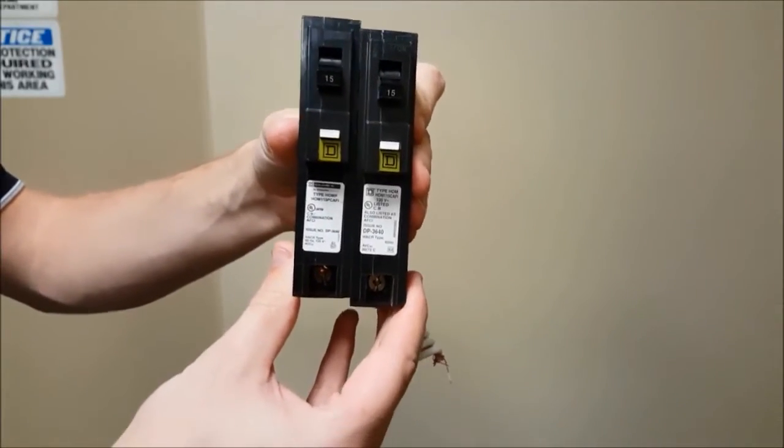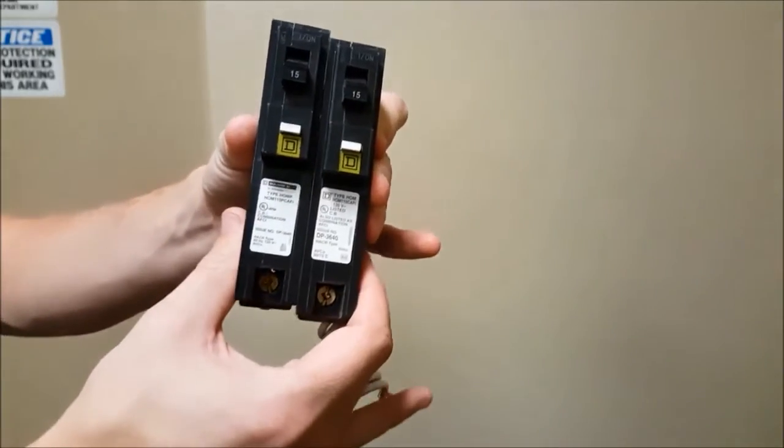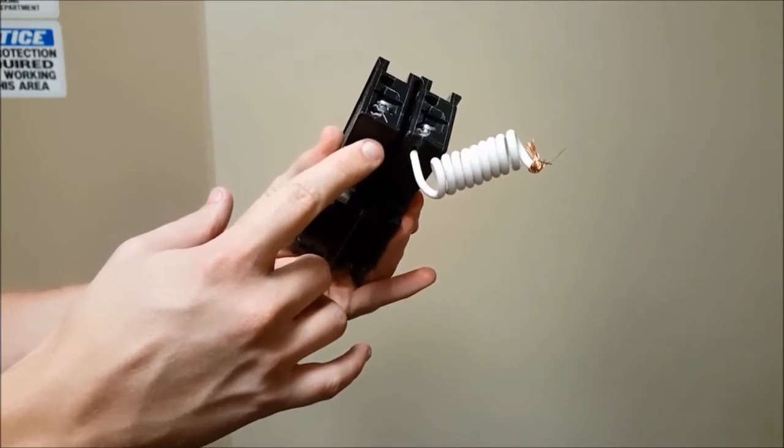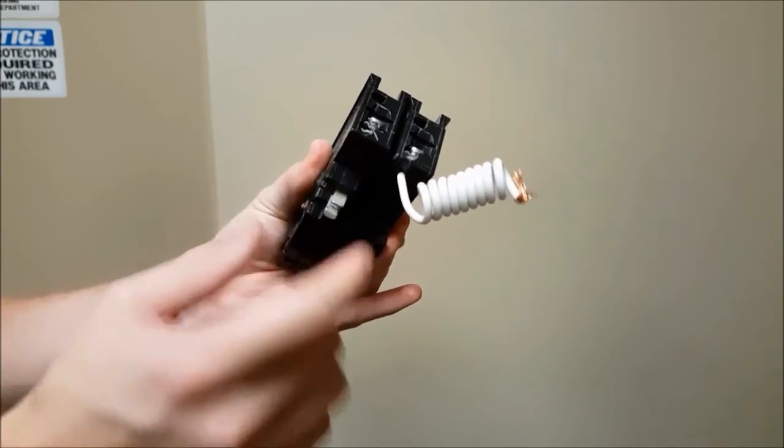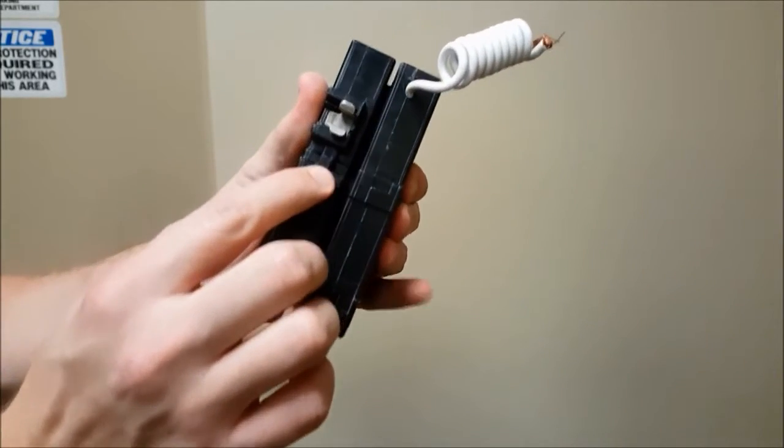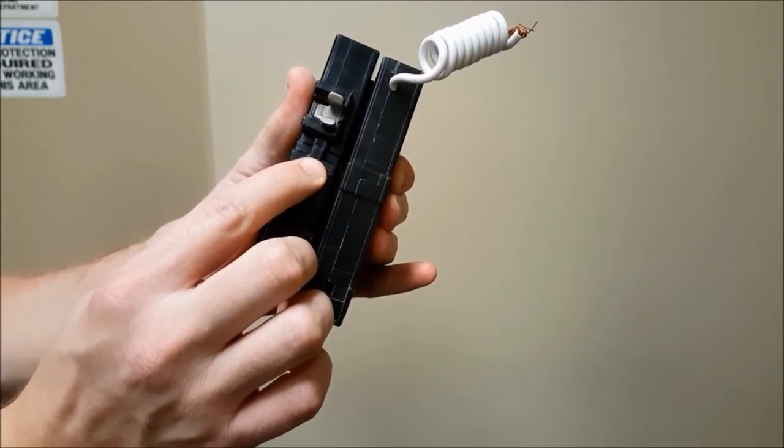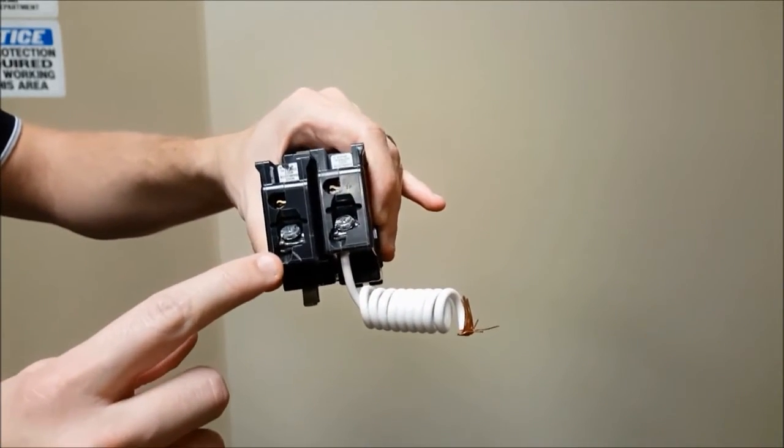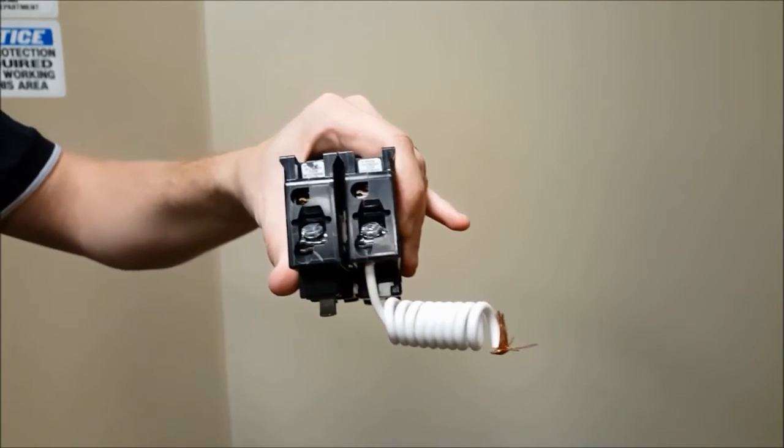You'll see that from the front the two breakers are about the same. The main differences will be the lack of the neutral pigtail on the plug-on neutral version as well as the rejection feature on the plug-on neutral version. Note that both breakers still have the load neutral connection for the load neutral from the circuit.